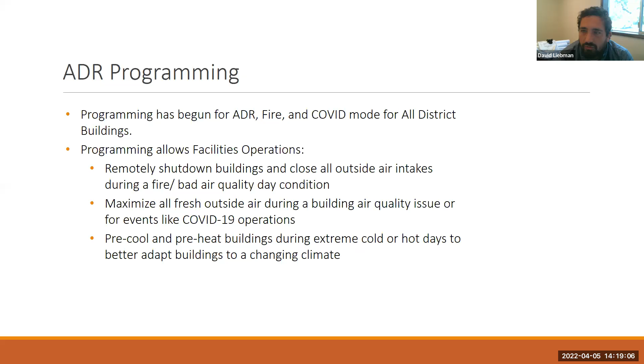Next we have an update on the automated demand response programming. That programming's been ongoing, updating all the buildings. As a reminder, it allows our buildings to be centrally controlled with a number of pre-programmed settings. We have a fire mode, which will unfortunately help us in the future, allowing us to instantaneously close all the outside air intakes so we're not bringing smoke into the buildings. We have a COVID mode, which allows us to pre- and post-purge air through the buildings around occupancy, and allow for 100% outside air. And then we have demand response, which allows us to respond to changing grid conditions should there be a microgrid event, before we'd have to disconnect buildings.